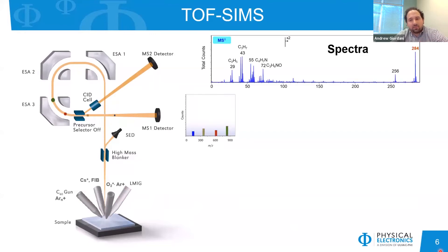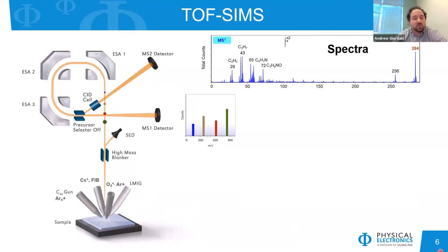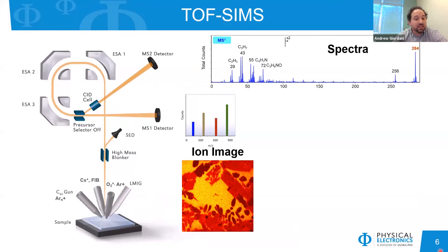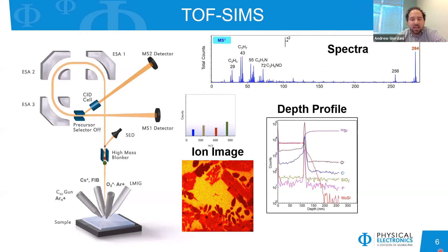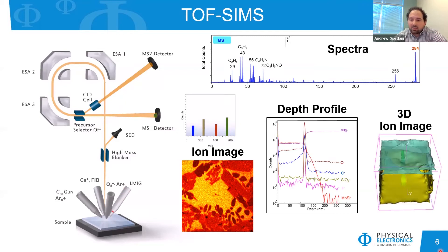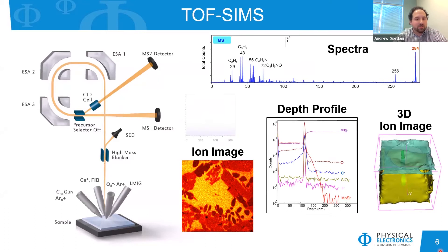From TOF-SIMS you can get surface spectra with good speciation of what's on your sample surface — both molecular and elemental information. You can also get ion images, since a mass spectrum is generated at every XY pixel as the analysis beam rasters over the surface, allowing you to see spatial distributions. You can do depth profiling to monitor species as a function of depth. All this information is stored, so you can reconstruct 3D images showing how species are spatially distributed in depth as well as in X and Y.